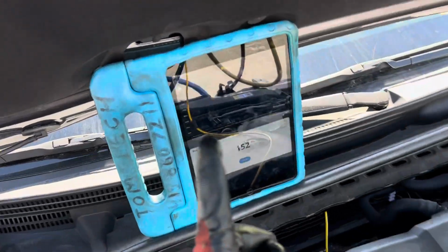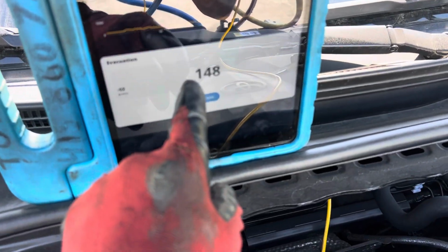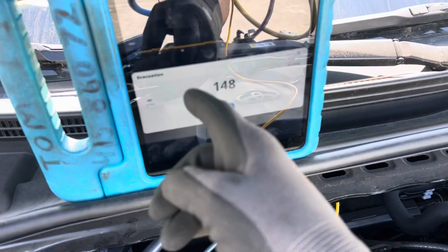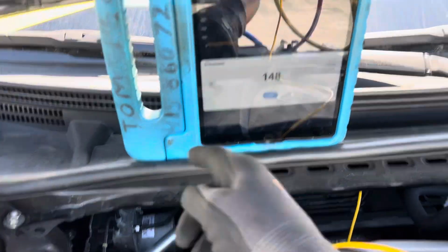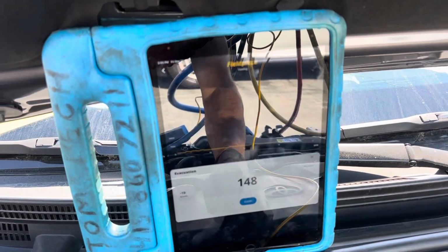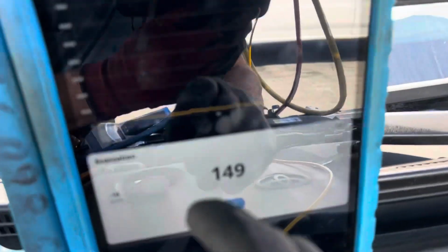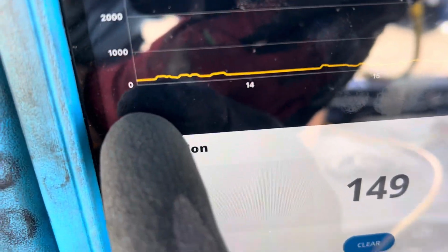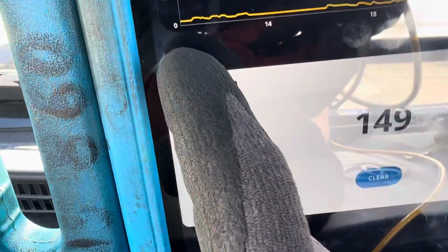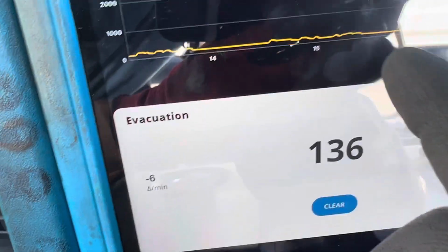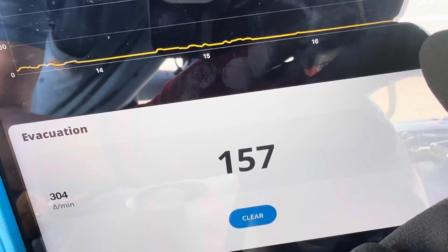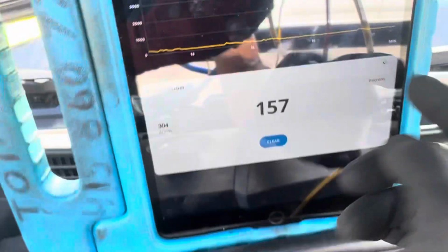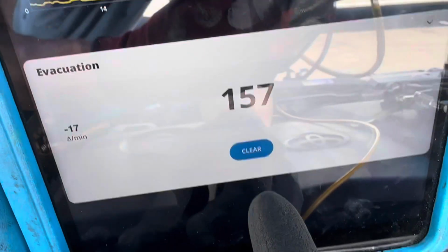So we seen video number 1, and we seen where the micron gauge went all the way up to 3400, and then I heated up the line and went above up to 6000 microns. Well, if you look right here, I turned it back on and redrew the vacuum. And from minute 14, 15, 16, going into minute 17, I put it back on the vacuum pump when we're down to 157 microns right now.